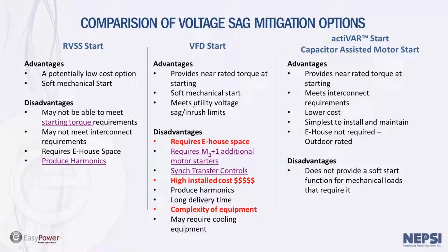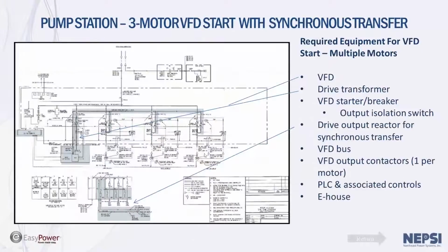In regard to the VFD starter, it is the gold standard, but it is also one of the more expensive options available for starting large motors. Typically, a VFD drive starter requires an E-house. It also requires N+1 additional motor starters for the application. It also requires sync transfer controls. This picture here shows the area in the blue is the extra hardware, switchgear and sync transfer bus required for a VFD starter.